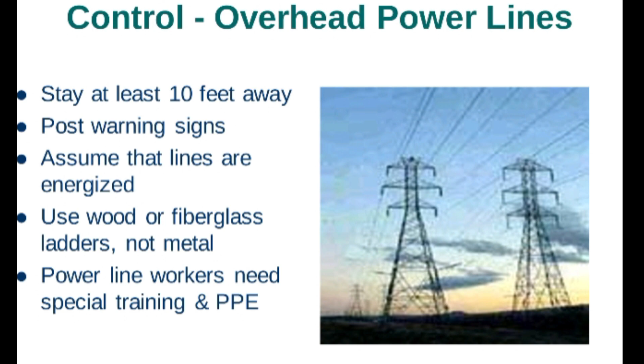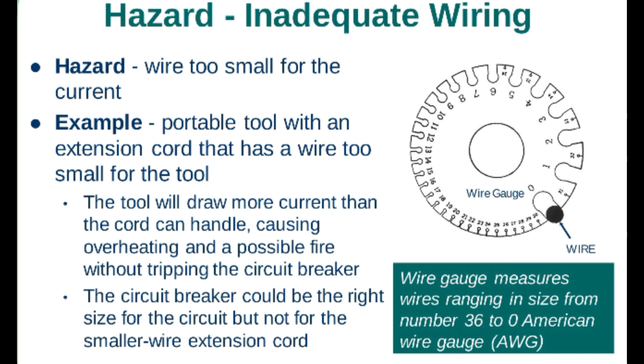Let's look at hazard: inadequate wiring. Hazard: wire too small for the current. Example: a portable tool with an extension cord that has a wire too small for the tool. The tool will draw more current than the cord can handle, causing overheating and a possible fire without tripping the circuit breaker. The circuit breaker could be the right size for the circuit but not for the smaller wire extension cord. You can see in the picture, wire gauge measures wire ranging in size from number 36 to 0, American Wire Gauge, AWG.